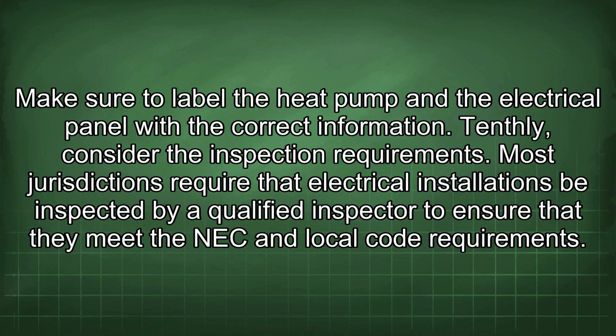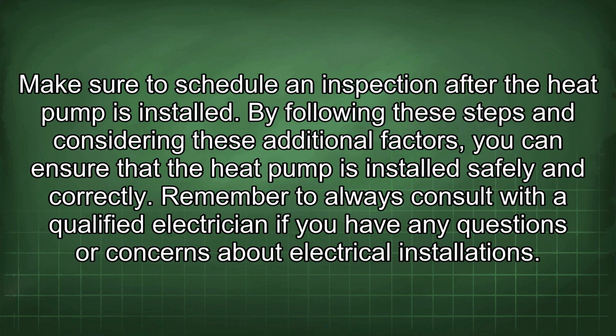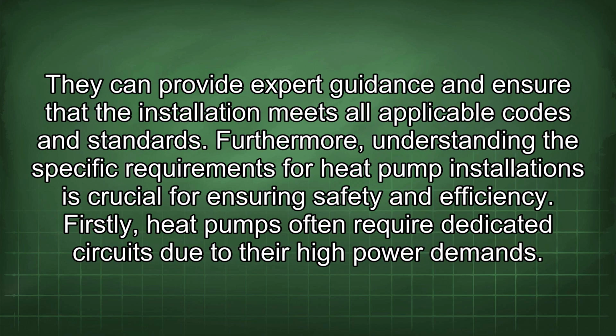10th, consider the inspection requirements. Most jurisdictions require that electrical installations be inspected by a qualified inspector to ensure that they meet the NEC and local code requirements. Make sure to schedule an inspection after the heat pump is installed. By following these steps and considering these additional factors, you can ensure that the heat pump is installed safely and correctly. Remember to always consult with a qualified electrician if you have any questions or concerns about electrical installations. They can provide expert guidance and ensure that the installation meets all applicable codes and standards.